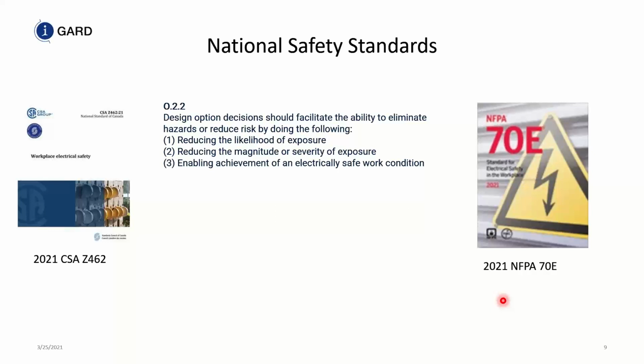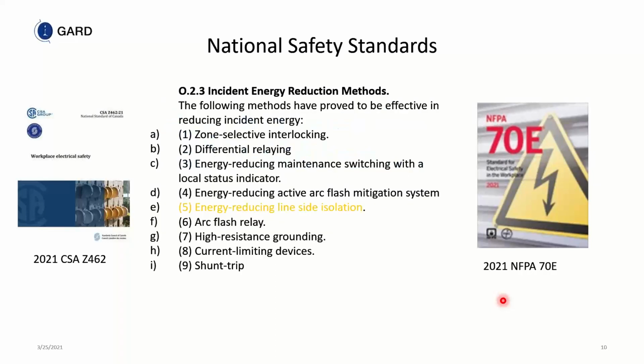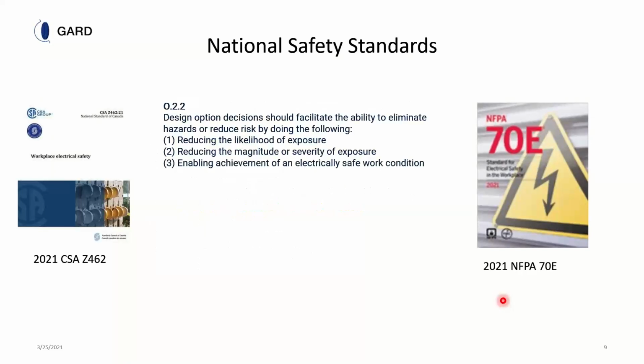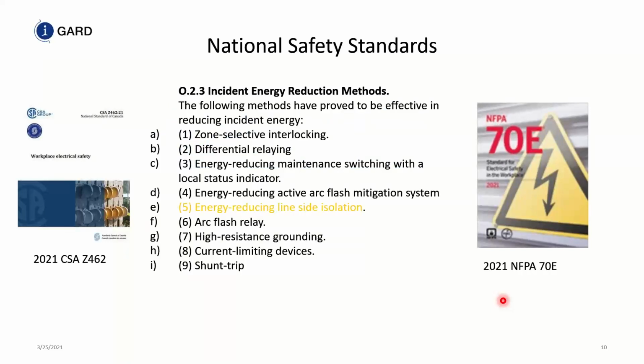So design engineers and consultants have the obligation to eliminate hazards or reduce risk by doing the following: reduce the likelihood of exposure, reduce the magnitude or severity of exposure, and enable achieving an electrical safe work condition. And regardless whether you're Z462 or 70E, both of these and 0.2.2 are exactly the same. 0.2.3 is also the same. The following methods have been proven to be effective in reducing incident energy.